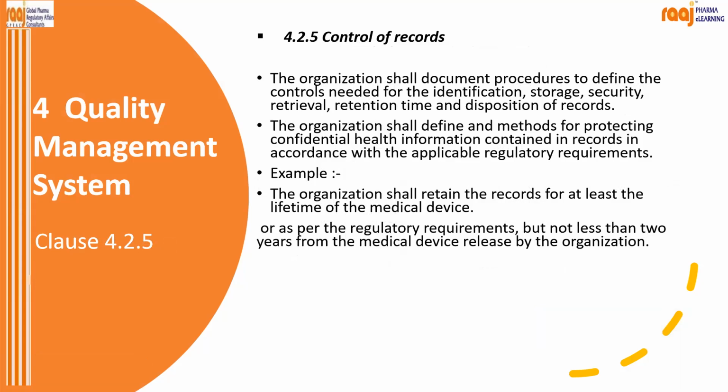Then come to control of records, right? Records, like whatever we entered, whatever record is generated, the organization shall retain the record for at least the lifetime of the medical device. So you have to define the retention: maintain our records for 5 years or more than that. When a clinical trial goes, they generally maintain them for 20, 30 years also, because sometimes the data is very useful. Sometimes a recall happens, then you reinvestigate.